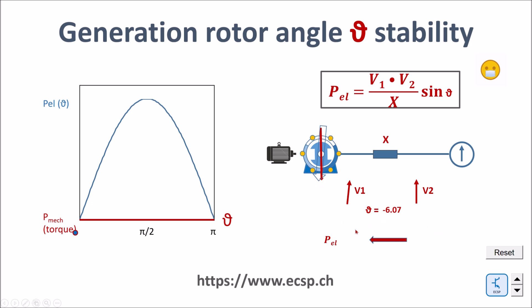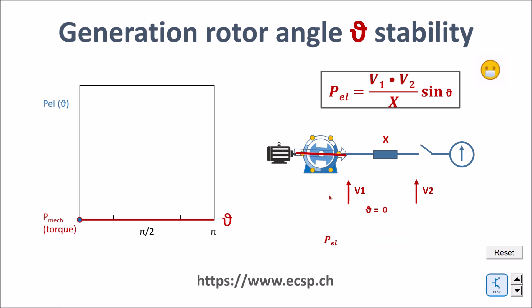The same angle also appears between the inner induced voltage of the generator and the voltage you can measure at the terminal of the generator. This angle at the closing instant, however, happens only if the two sources — namely the generator and the grid — are not exactly synchronized at the closing instant of the breaker. If we do not hit the optimal synchronization point when we close the breaker, there will be an initial oscillation of the rotor angle until perfect synchronization.